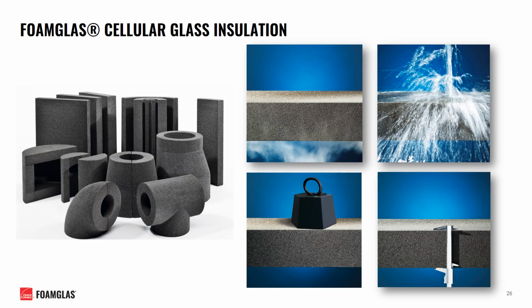Foam glass is completely impermeable with a water vapor permeability rating of 0. It does not require the use of an external vapor barrier to achieve this, as the insulation itself acts as its own vapor barrier. It also boasts a relatively high compressive strength when compared to other insulation materials in the industry, making it suitable for direct buried and pipe support applications. It's also very dimensionally stable, having a thermal expansion coefficient similar to that of carbon steel, making it suitable for wide temperature cycling applications.